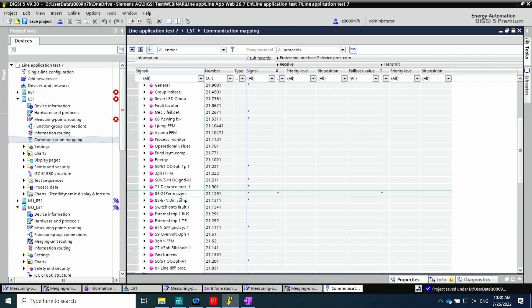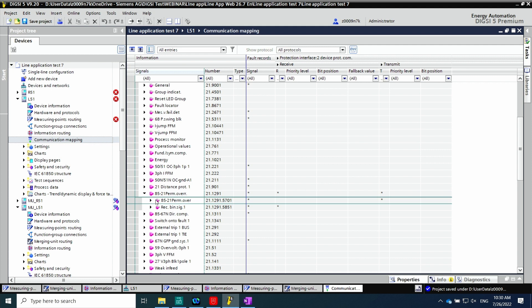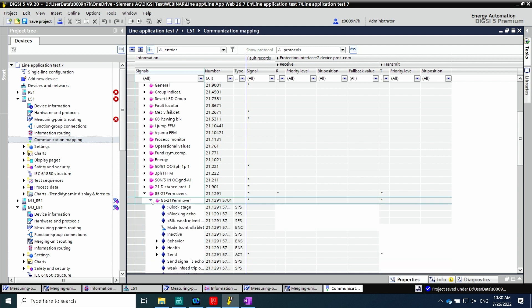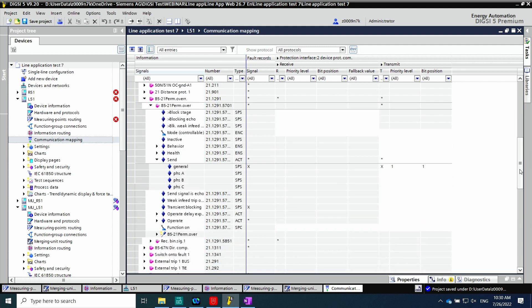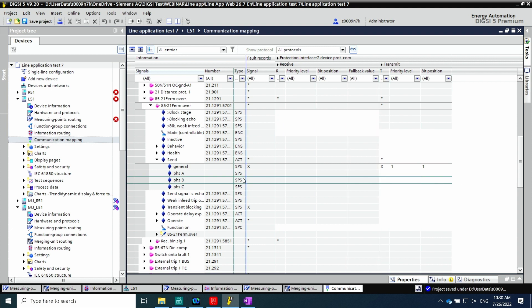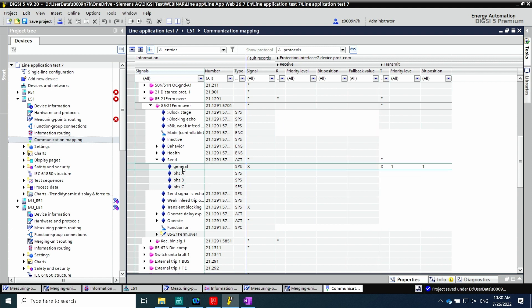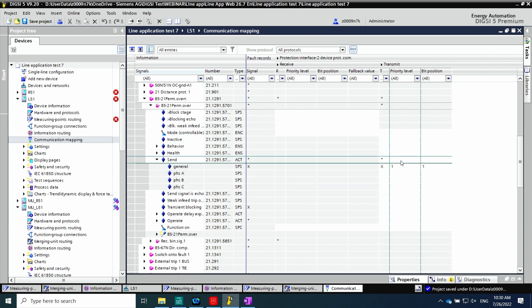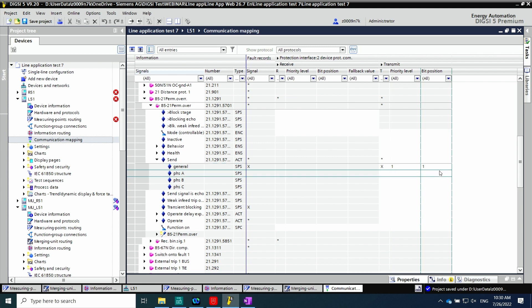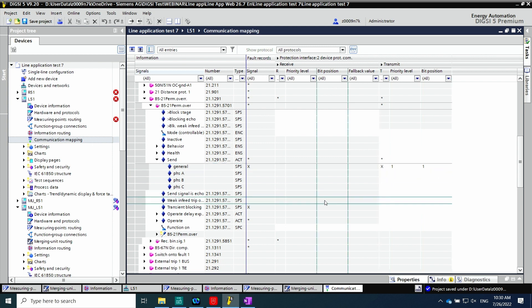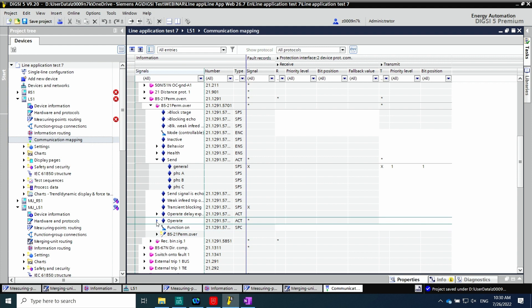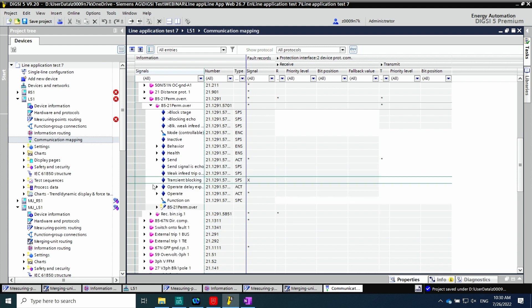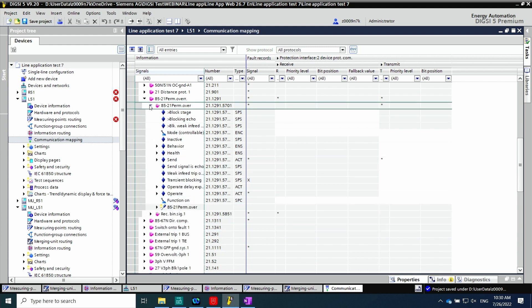In the function group line, the distance protection and teleprotection schemes to be used can be found. We will map the signal we want to send — in this case, send general with priority one. SIPROTEC can also receive the information in the teleprotection scheme that is enabled here. The protection interface is required for line differential protection and teleprotection schemes, all done with SIPROTEC 5 7 SL 87.